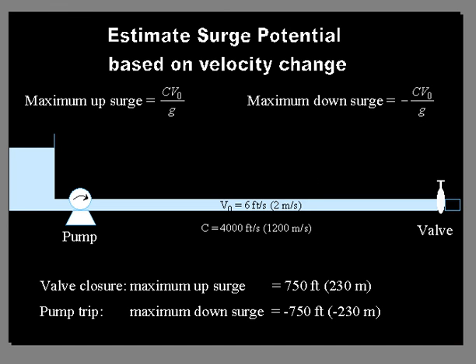Here, we can use this simple approach to estimate the effects of a surge. For example, the maximum upsurge due to the closure of a valve, if you have initial velocity of 6 feet per second or 2 meters, we can calculate it from this simple equation. It would be about 750 feet or 230 meters. The maximum downsurge also is computed based on the velocity change, and that would be minus 750 feet or 230 meters. So it's very significant, and this very simple calculation can help you estimate that.